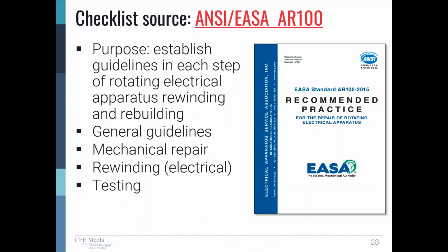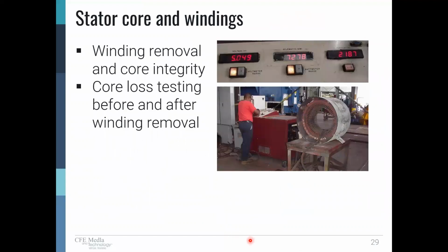The source document for the checklist, ANSI EASA AR100, its stated purpose is to establish guidelines for each step of rotating electrical apparatus rewinding and rebuilding. And by rotating electrical apparatus, it's not just motors, it's also generators. It's broken up into 4 major sections: general guidelines, mechanical repair, rewinding, which is the electrical aspect, and testing. Since the accreditation program relies on AR100, what we're talking about here isn't just the accreditation program, but also some of the contents in AR100, the good practices from AR100.